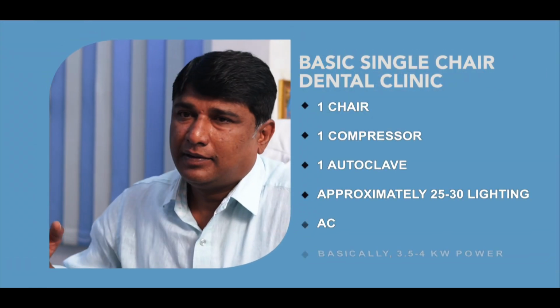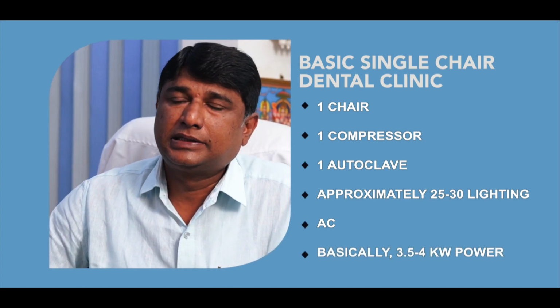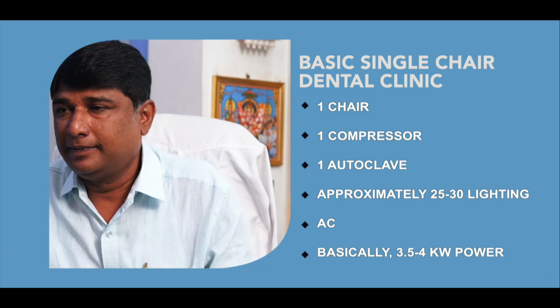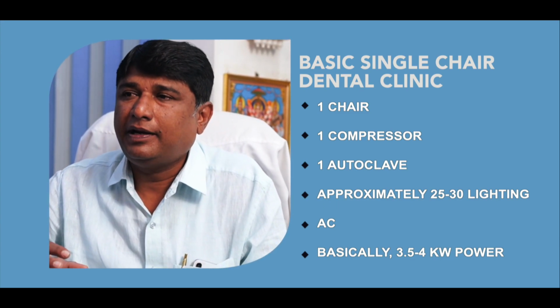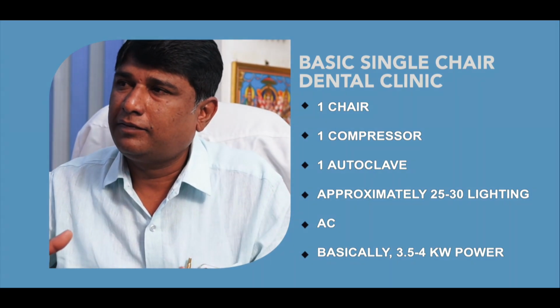So my first question, Dr. Harish, why do you think power supply is important? Yes, that's actually a very nice question, Dr. Prince. See, if you want to set up a basic single chair dental clinic, the first thing you'll have to notice is the power given to your clinic or premises. That includes how many kilowatts you require to run a successful dental clinic with one chair, one compressor, one micro unit, one autoclave, as well as approximately 25 to 30 lighting points and an AC. So you would basically require somewhere around 3.5 to 4 kilowatts of power.